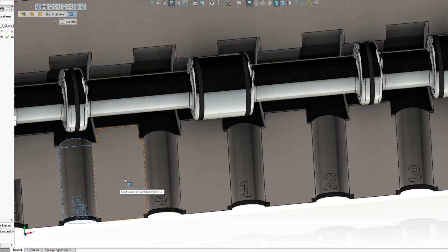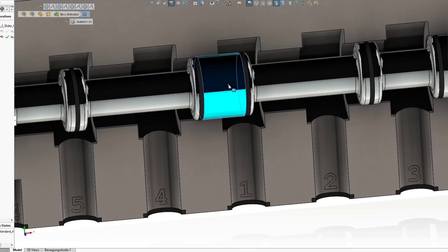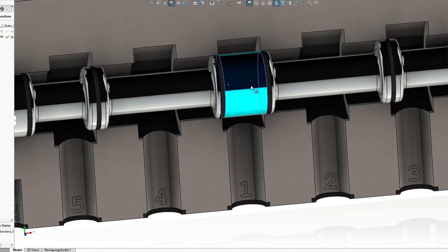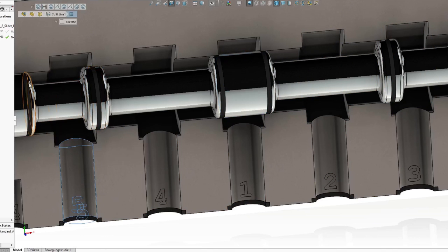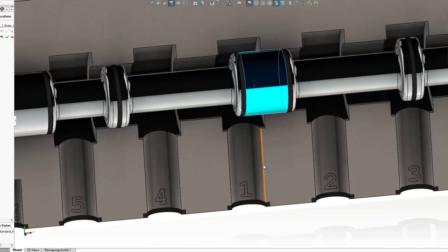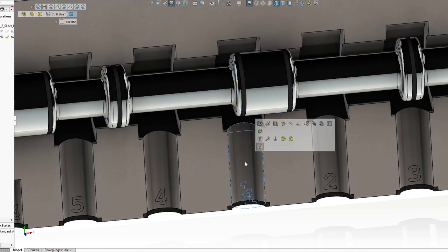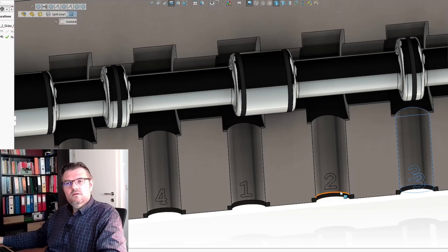If we move the piston to the other side, right now in the middle position, all ports are sealed to the right and to the left: 1 is sealed, 4 is sealed, 2 is sealed, 3 is sealed, 5 is sealed, everything is sealed without overlapping. This switching is without overlapping. And then, going to the other extreme, now 1 is connected to 4, 5 is sealed, 2 is connected to 3.